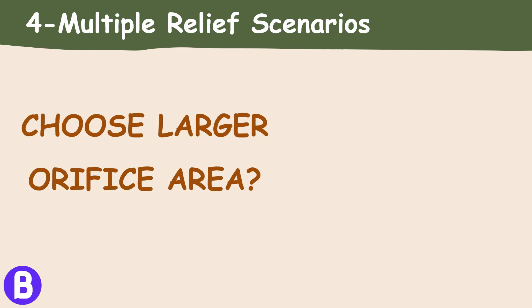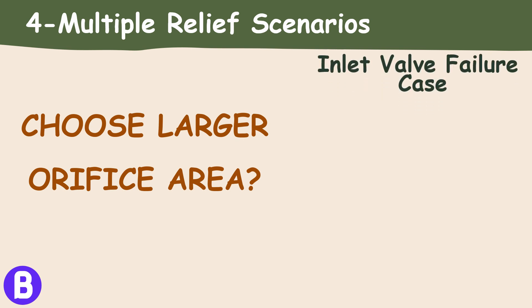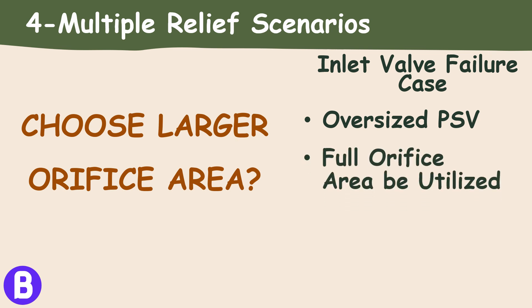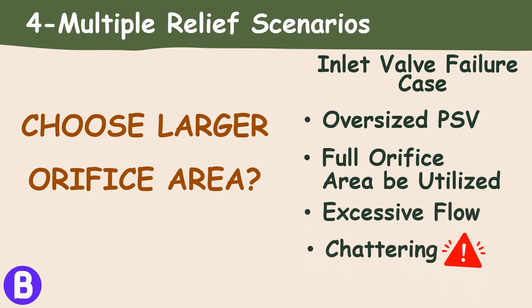If we chose to size the PSV for the larger scenario and select the larger orifice area, this would mean that in the event of an inlet valve failure, the PSV is oversized. An oversized PSV means that when the PSV opens, the full orifice area shall be utilized, causing excessive flow to pass through the PSV. This can cause PSV chattering, which can lead to damage in the long run.